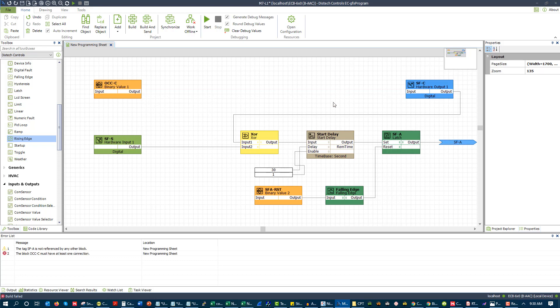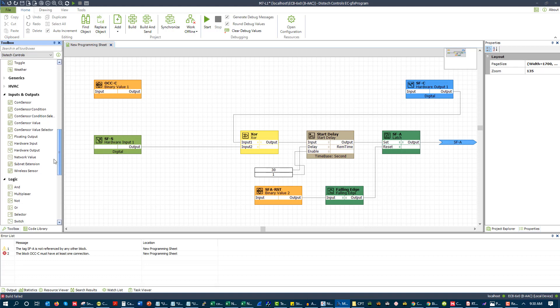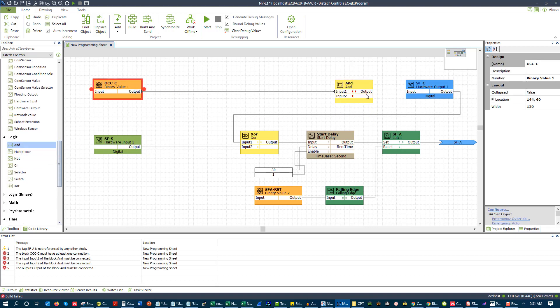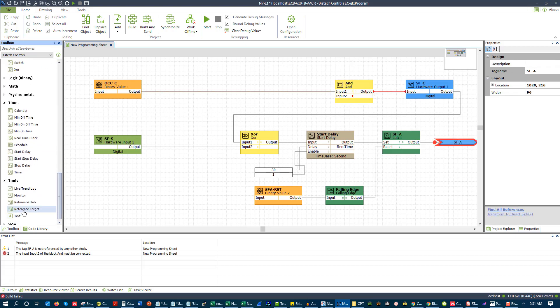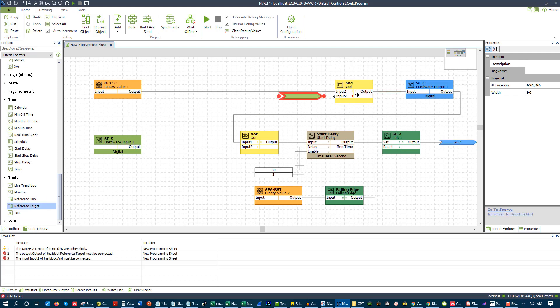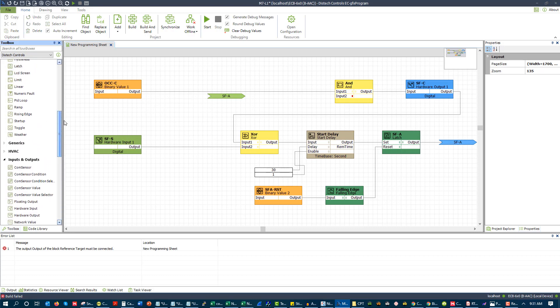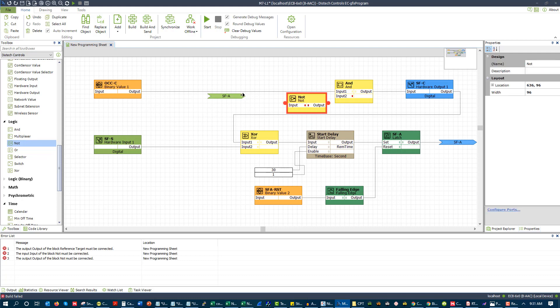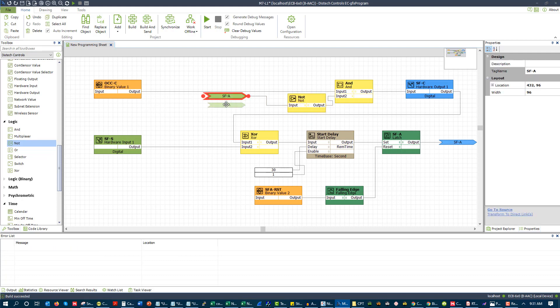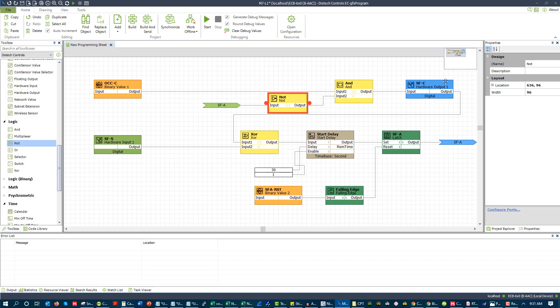And then we would actually go and delete this right here. We could then take our reference target — SFA — and put a NOT in here. There we go. And there you have it. This pattern right here will say: as long as we don't have an alarm and we have our command, our supply fan runs. So if we build this, it's all good. And here's our alarm right here, looking at output as well as supply fan status. So if someone put this in hand, or for some reason we're getting status even though it wasn't on, or it was on and we weren't getting status — it's all right here.